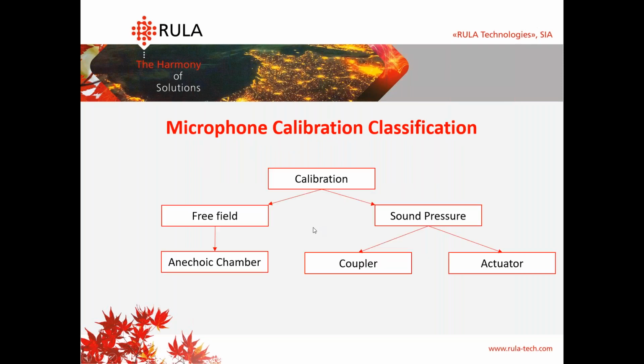Our first step is to classify the ways you can calibrate your microphone. Here you see that we can divide all the calibration methods into 2 groups. The first one uses the free field, and the second one uses sound pressure. As I can see on the screen, it seems that calibration by sound pressure is a little bit more complex. Am I right, or are they the same? These calibration methods are based on different principles, which I'll describe a bit later, and they use different equipment. For example, for free field calibration, we use an anechoic chamber, and for sound pressure calibration, we can use a coupler or a sound actuator.